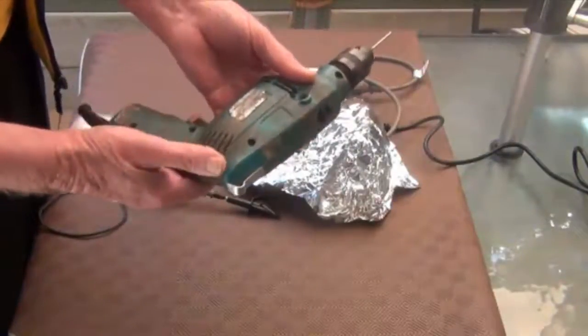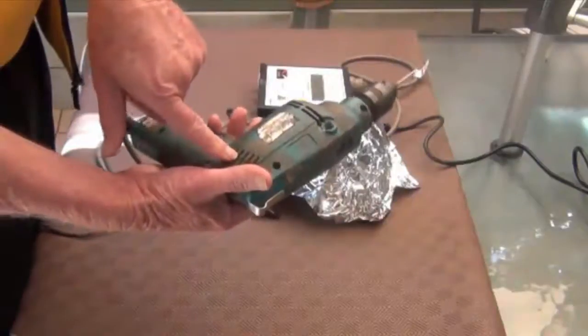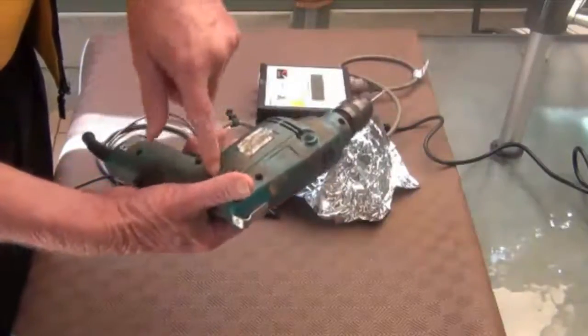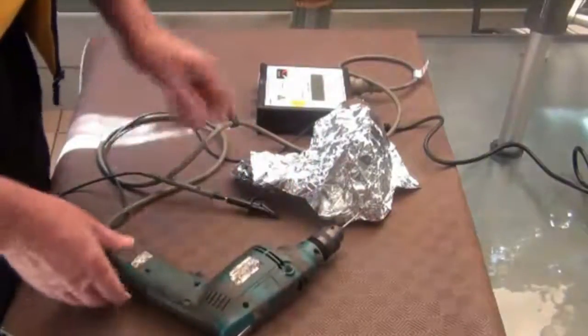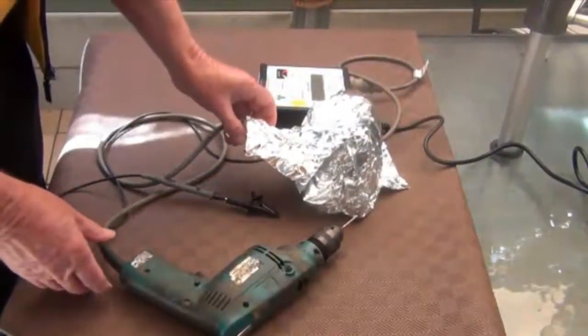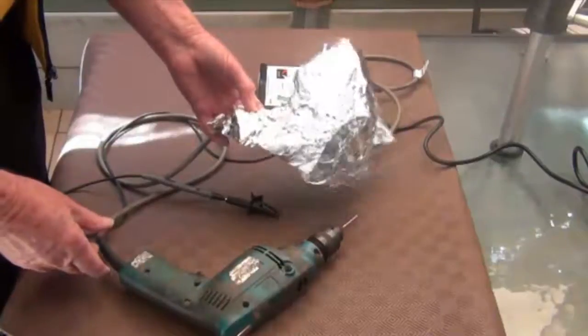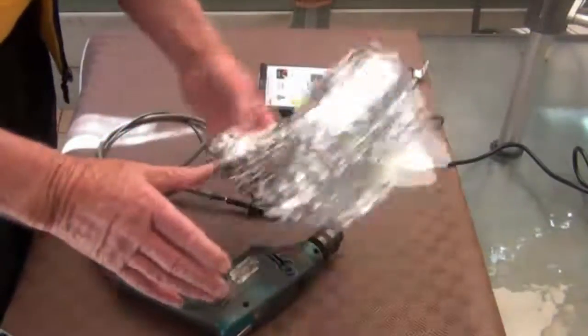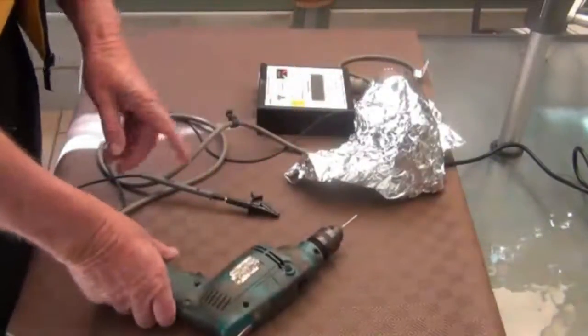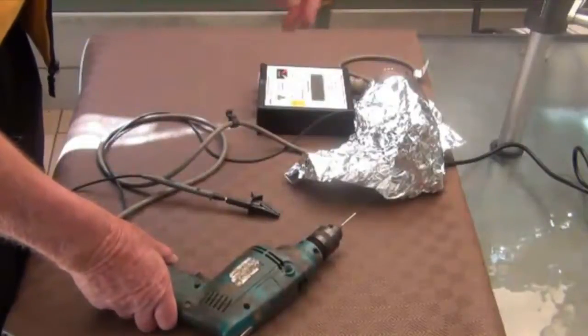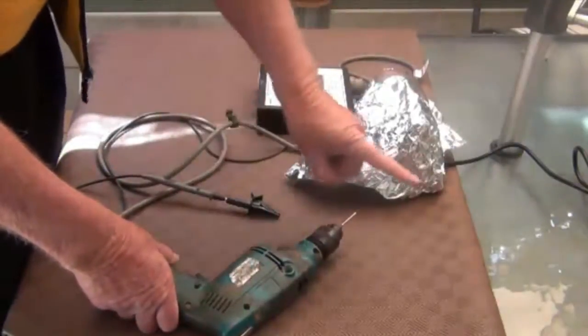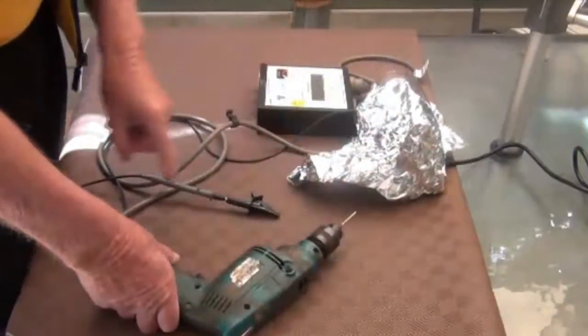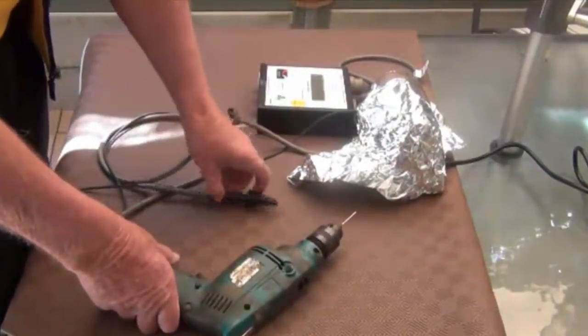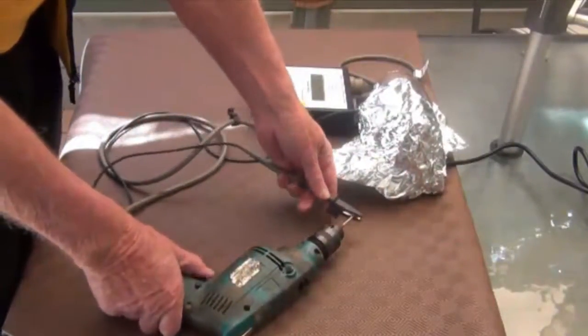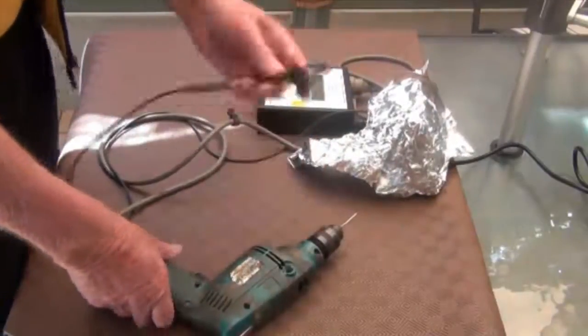There might be a bit of dirt, or sometimes in the back here you get a build-up of carbon dust off the commutator. But regardless of which method you use, the aluminium foil or the butcher's paper, it does not take the place of connecting your probe to any exposed metal. You must still do that.